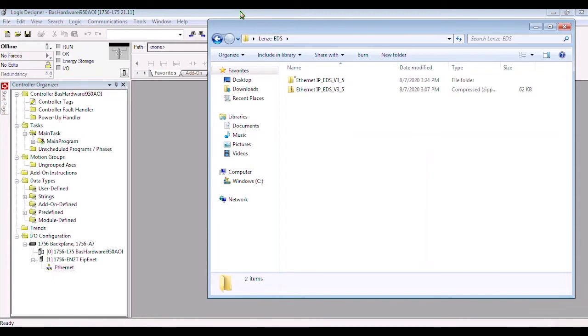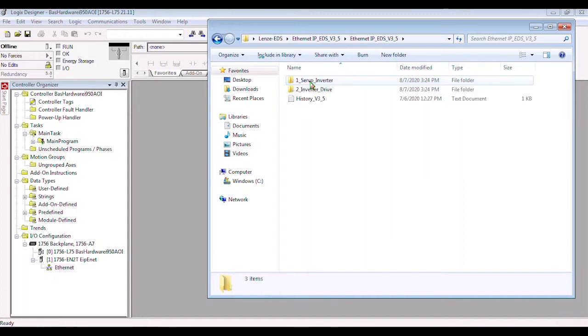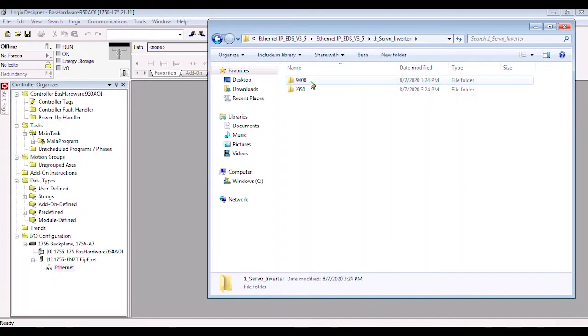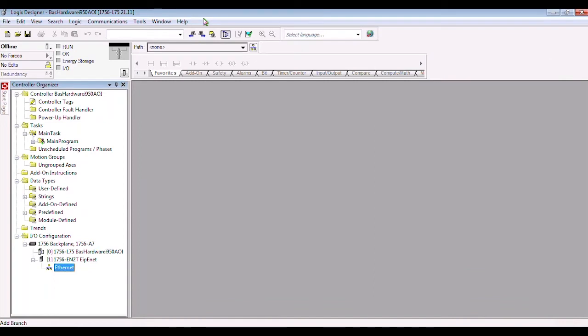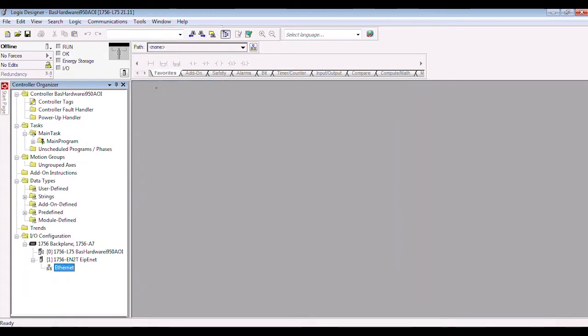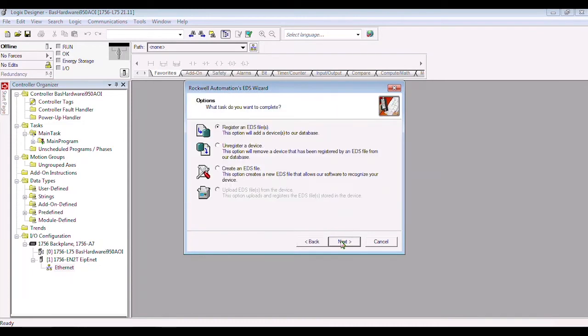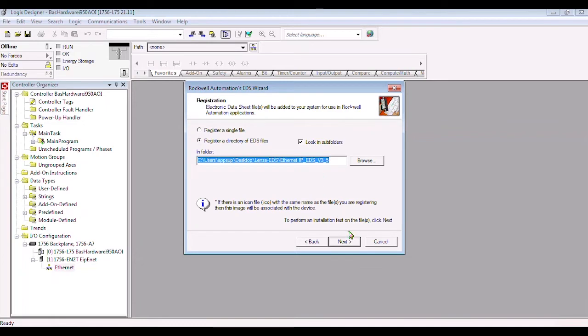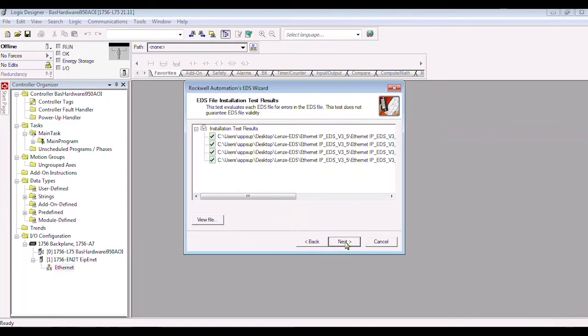Once you unzip the file, you'll find that it includes EDS files for other Lenze devices as well. For the i950, it should be under the Servo Inverter folder. In your Rockwell software, go to Tools and click on EDS Hardware Installation Tool. A wizard window should pop up. Click on Register an EDS file and navigate to the folder you have previously downloaded. From here, you can follow the rest of the instructions on the wizard to install the EDS files onto your computer.